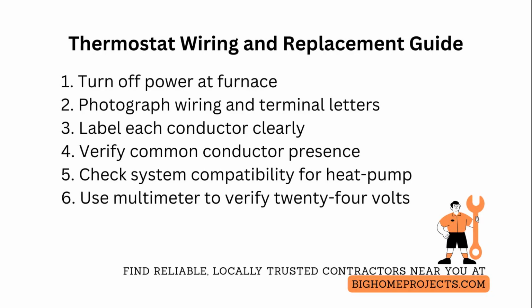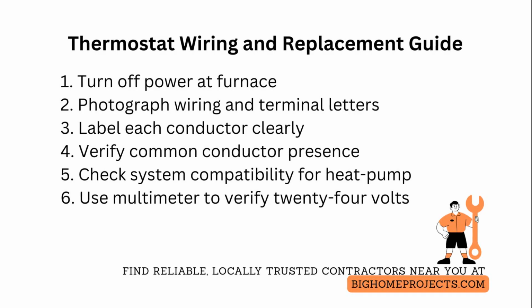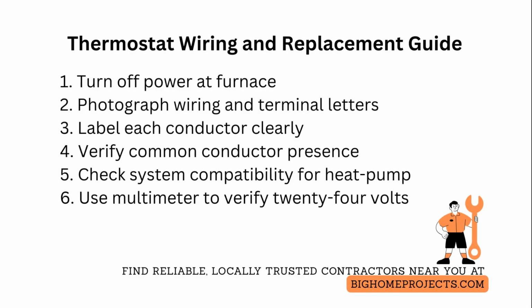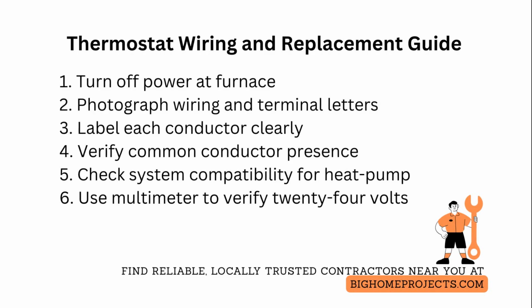If the old thermostat used a mercury switch, note that the mercury device likely used 2 terminals that completed a circuit differently than modern solid-state controls. Map those terminals to the new stat by tracing which 2 wires were connected during heating and cooling calls. Use a multimeter to verify 24-volt alternating current presence across the R and C terminals before finalizing installation.